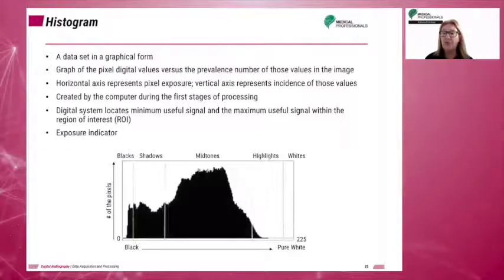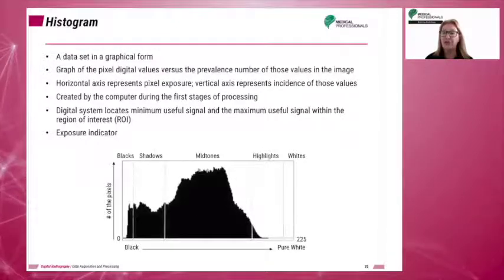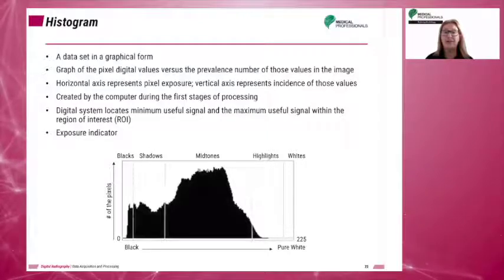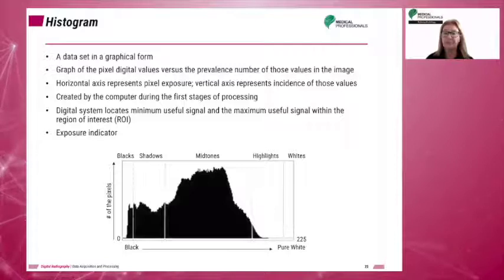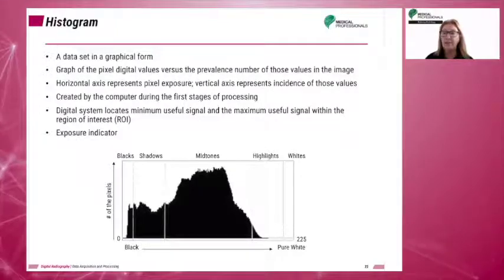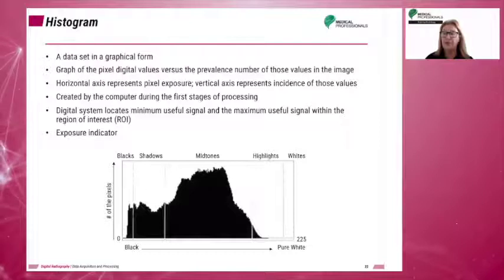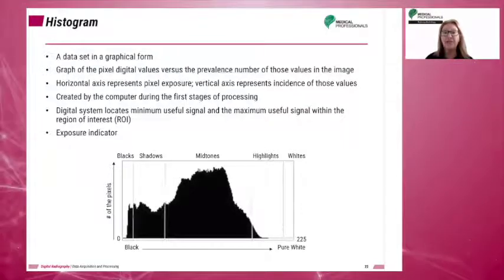Histogram analysis is accomplished through the use of complex mathematical calculations, or algorithms, that allow the exposure histogram to be compared with reference histograms stored in the computer. The histogram is a graph of each unique digital value displayed by the pixels and the number of times that value occurs in the image data. The computer uses the shape of the histogram and the algorithm to locate the values of interest and determine the exposure indicator.